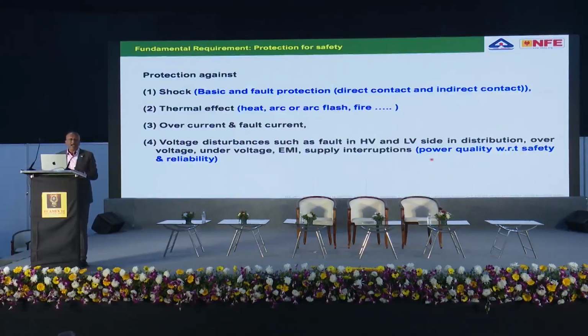So basically, every electrical installation needs protection against shock, protection from thermal effect, meaning heat and arcing, overcurrent and fault current, and voltage disturbance. These are the 4 fundamental requirements of electrical safety in every electrical installation. The idea is nobody should get shock, no fire from the electrical installation, no overcurrent, because overcurrent or short circuit current will sometimes create thermal effect or electromechanical forces, and voltage disturbances.